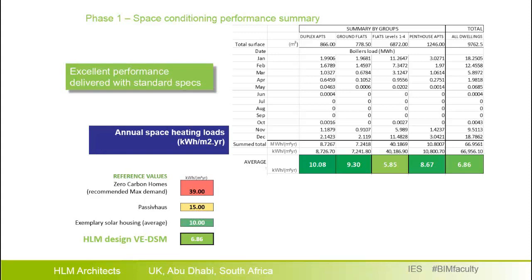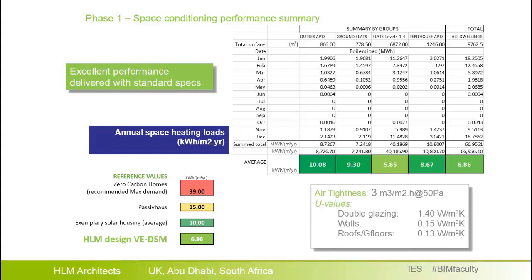Most importantly, this performance was obtained without any special specification in the fabric or glazing beyond high air tightness — more or less standard values, still good of course. It is interesting that we are achieving this with standard double glazing, while a Passive House scheme would have required triple glazing as mandatory. This is what we think is the difference provided through detailed analysis.